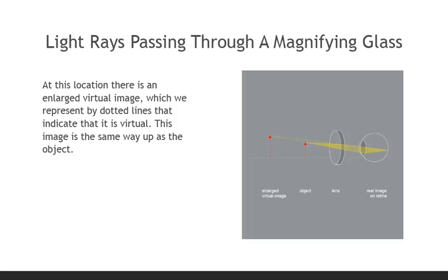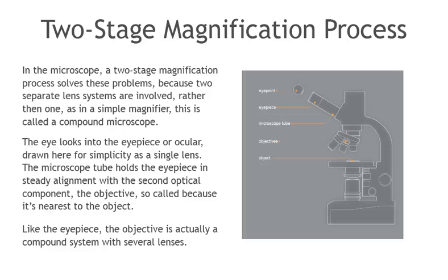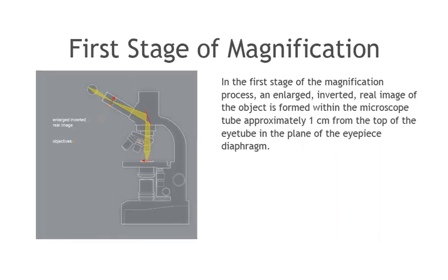In the microscope, a two-stage magnification process solves these problems because two separate lens systems are involved rather than one, as in a simple magnifier. This is called a compound microscope. The eye looks into the eyepiece, or ocular, drawn here for simplicity as a single lens. The microscope tube holds the eyepiece in steady alignment with the second optical component, the objective, so-called because it is nearest to the object. Like the eyepiece, the objective is actually a compound system with several lenses. In the first stage of the magnification process, an enlarged, inverted, real image of the object is formed within the microscope tube, approximately one centimeter from the top of the eye tube, in the plane of the eyepiece diaphragm. This is the function of the objective. The object is represented by a solid red arrow, and so is the real image.